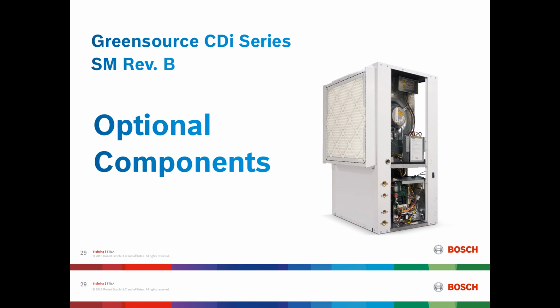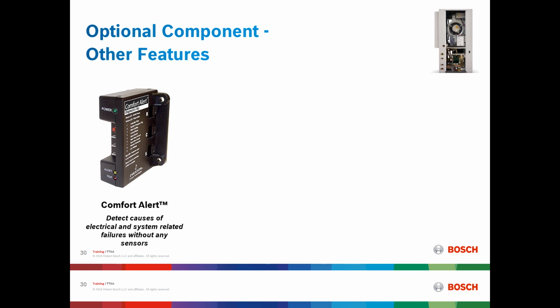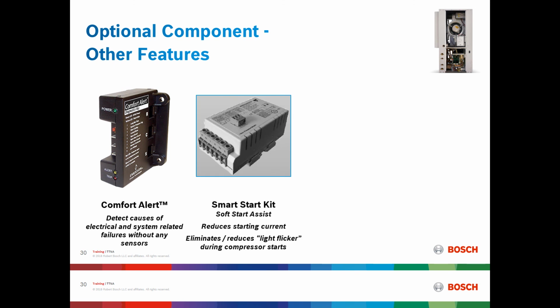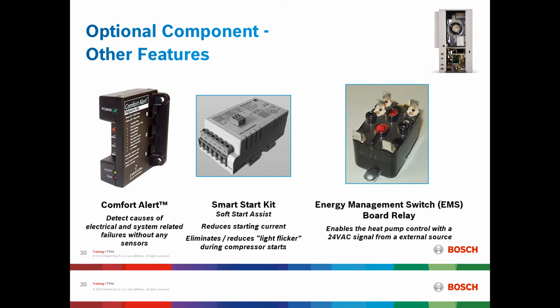Now let's look at the optional components that can be ordered with the Rev B model. These will include the Comfort Alert diagnostic device that detects causes of electrical and system-related failures without any sensors. The unit can have a Smart Start kit or Soft Start Assist that reduces starting current and eliminates or greatly reduces light flicker that could occur during compressor starts. The unit also can be provided with an energy management switch or EMS board relay that enables the heat pump control with a 24-volt signal from an external source.